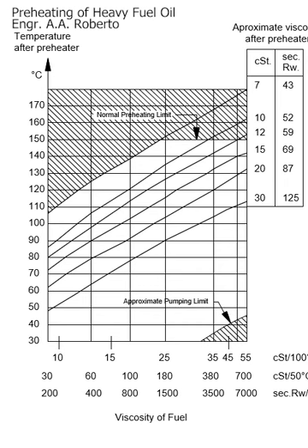Good day, students. Today, our discussion is all about the viscosity of the fuel, how to set our viscosity controller by changing the temperature based on the required viscosity. So, on board the ship, we are maintaining the viscosity from 10 centistokes or CST up to 15 centistokes only.